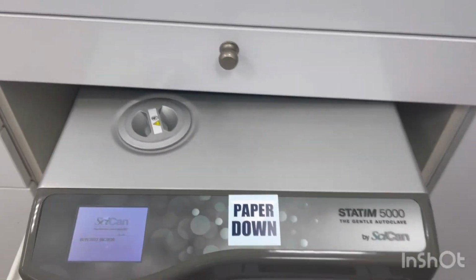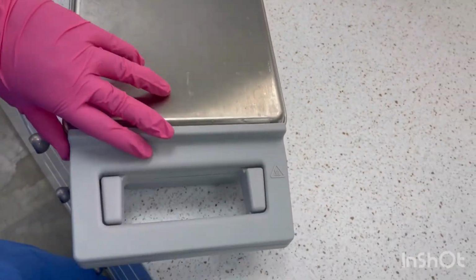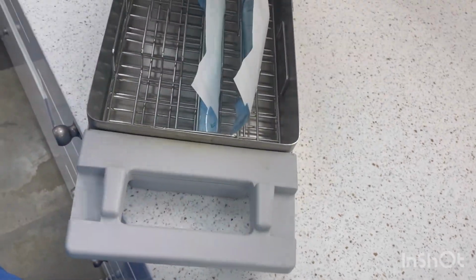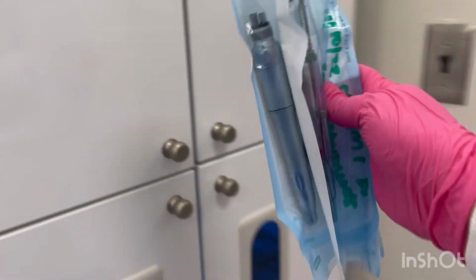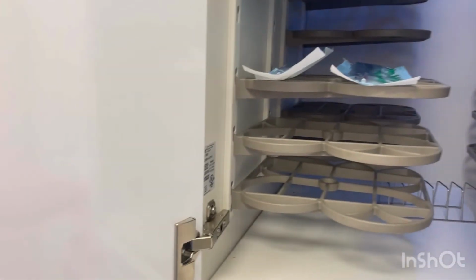This is where the clean instruments are held. After your instruments have run through their cycle in the Statim, you can retrieve those as well. Make sure to also check the indicator in the packaging through the Statim to ensure that they are sterilized. If the indicator suggests that they're sterile, you can then proceed to put them in the storage area in the blue zone, which is the clean side of the sterilization room. When instruments need to be retrieved either in the morning or throughout the day for patients, they can be easily found in this blue storage area.